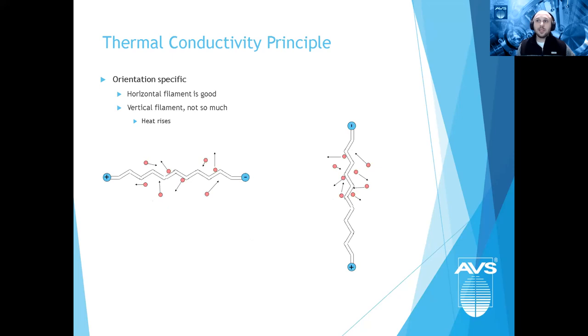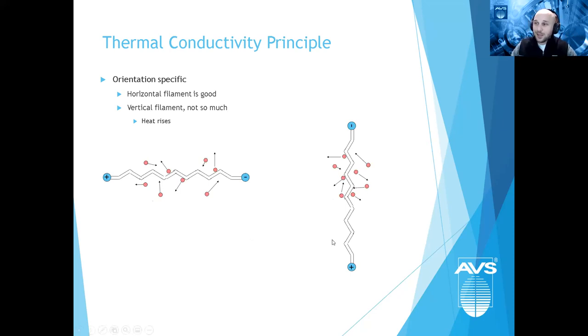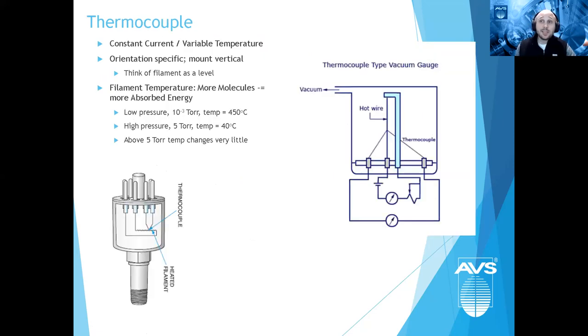Pirani or convection-enhanced Pirani gauges use constant temperature — the filament is kept at a constant 105–150°C — and based on molecular interaction absorbing energy, the gauge requires higher or lower current to maintain that constant temperature. Molecules absorb energy at different rates, which is why gas composition matters; these gauges are calibrated in nitrogen. Thermal conductivity gauges with filaments are also orientation specific — they typically prefer to be horizontal. If vertical, heat rises and part of the filament is not properly interacting with molecules, skewing the measurement.